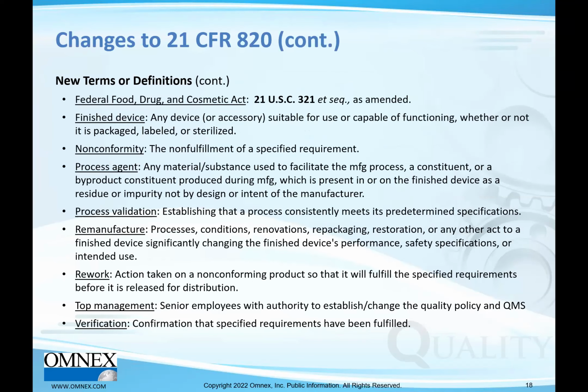New terms and definitions continued. We have the Federal Food, Drug, and Cosmetic Act. It is referenced in here and is normative to CFR 820. And that can be found on the FDA.gov. Finished device, any device or accessory suitable for use or capable of functioning, whether or not it is packaged, labeled, or sterilized. So if you have accessories or ancillary components for a device coming in from the United States and it is not labeled as such, it may be quarantined at customs, and you'll need to identify that properly. So finished devices include ancillary or accessory devices or components.